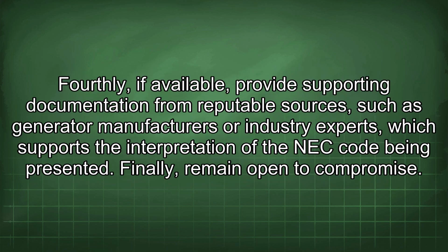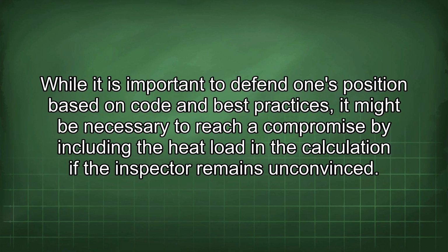Fourthly, if available, provide supporting documentation from reputable sources, such as generator manufacturers or industry experts, which supports the interpretation of the NEC code being presented. Finally, remain open to compromise. While it is important to defend one's position based on code and best practices, it might be necessary to reach a compromise by including the heat load in the calculation if the inspector remains unconvinced.